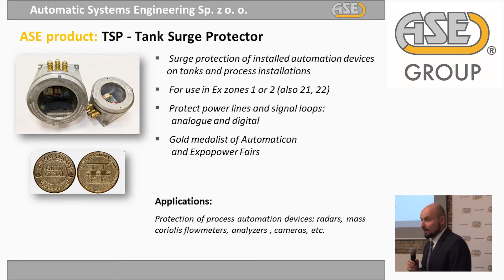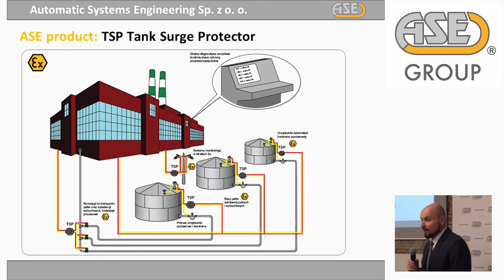Where to install it? Some examples: very close to the radar on the tank, very close to the cameras in the Ex zone, or the fire detectors, or very close to the valves or flow meters. Normally it's installed somewhere in the control room, close to the safe area, but that's not real protection. Here, close to the device, it's the real protection.